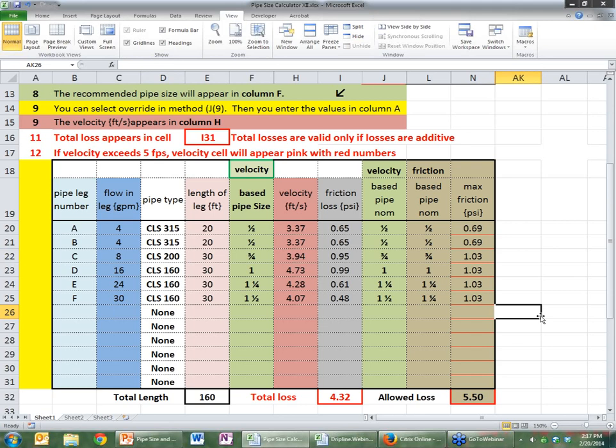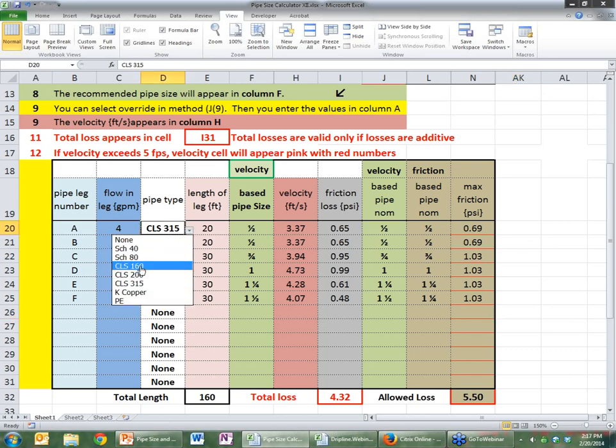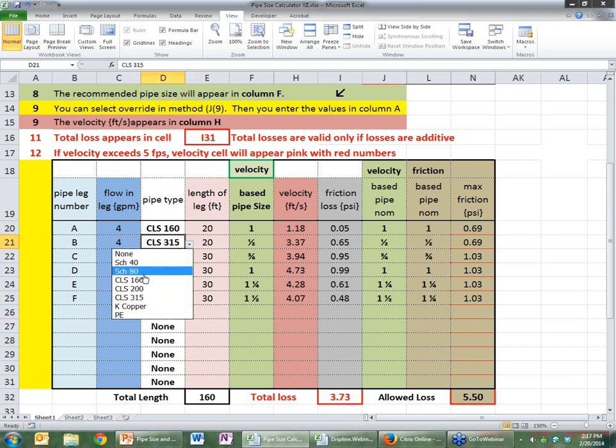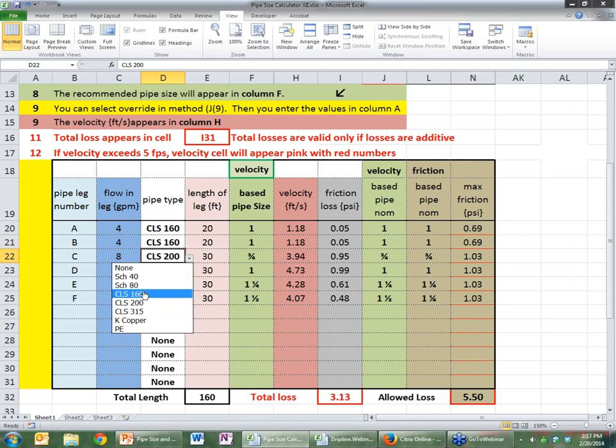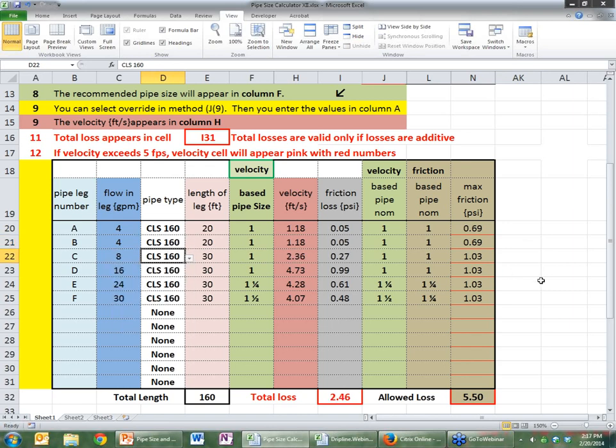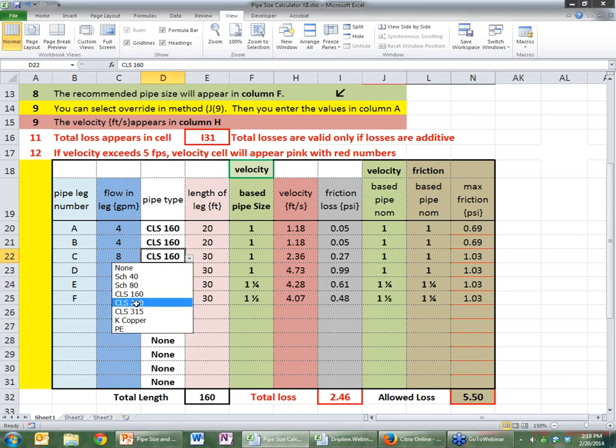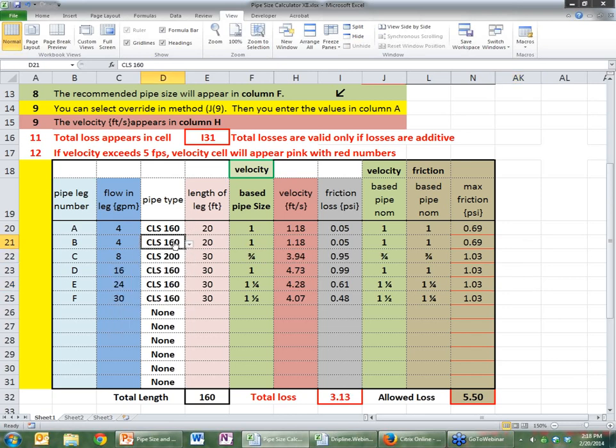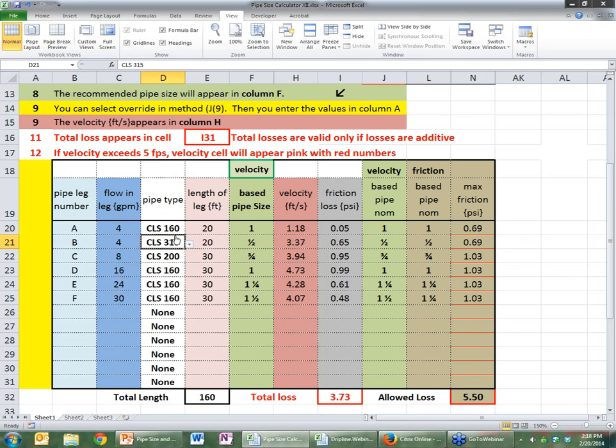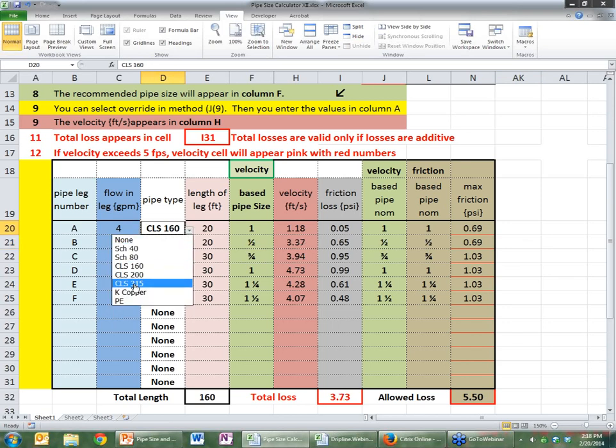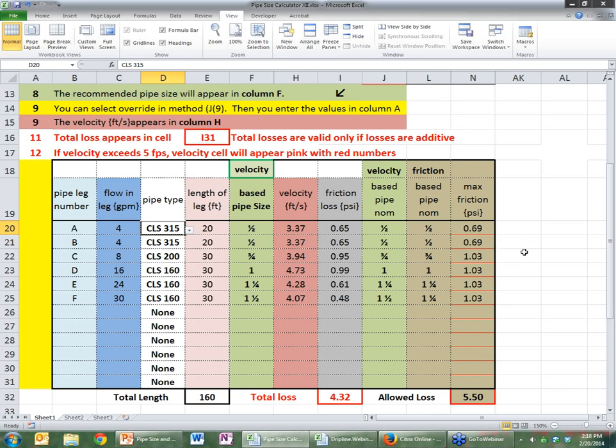The reason is, in most parts of the country, the smallest pipe size available in class 160 is 1 inch. 200 is available in 3 quarters. But 200 is not available in half. So if I made all of these 160, these sizes would be 1 inch. Now, it's not absolutely true because I did a little bit of web searching, and it looks like from some suppliers you can get some other sizes. But that's the reason this was done this way. So let's change them back to 315.